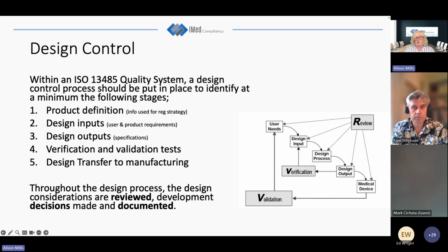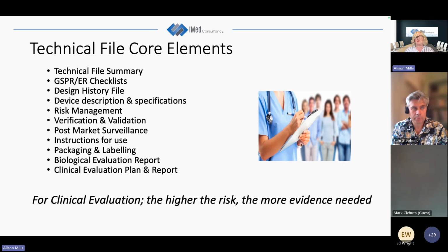Within the design of your product, you need to think very much about how your design controls happen. We get a lot of clients that come to us where something hasn't worked when they've tried to reproduce it, so they change the product. No, no, no, it's meant to be the other way around. You design the product to do what it's supposed to do. I'm sure Andy's hearing this and remembering clients where this has been the case. And then you want to make it perform to the expected performance and do the things that it should do. So this all is documented in your design history file, and your QMS will retain all the documentation and evidence for that. I'm not going to go into every part of this.